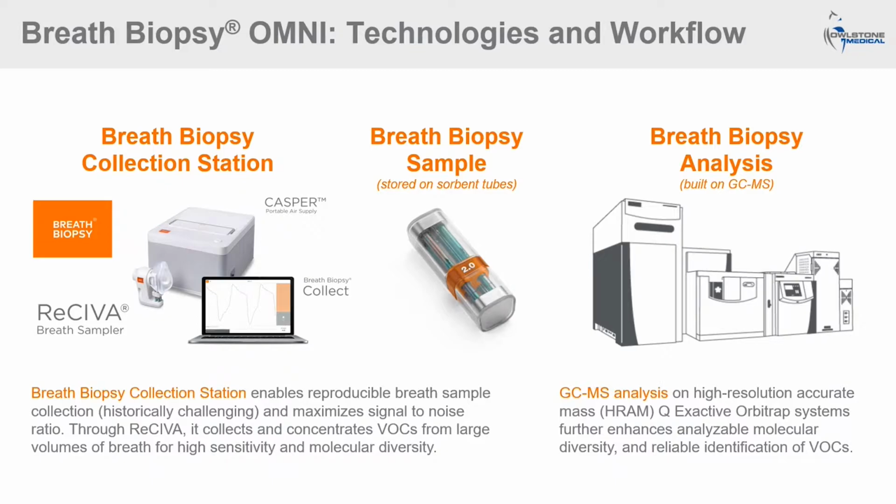So just to briefly talk through this, there's a Breath Biopsy collection station, which includes the ReCIVA breath sampler, which allows for a reliable collection of a large volume of breath, pre-concentrating and stabilizing those volatile organic compounds collected from the patient onto a Breath Biopsy cartridge, which is effectively sorbent tubes, which can then be shipped back to our lab in Cambridge.